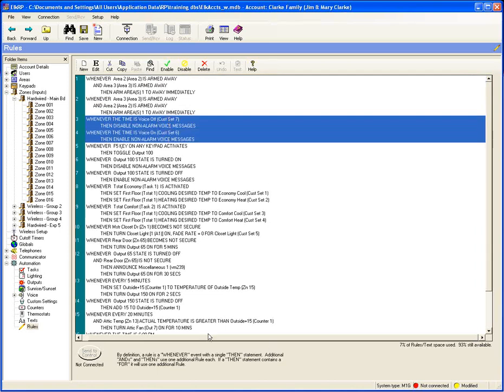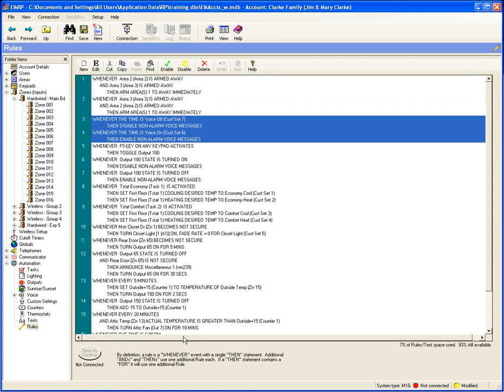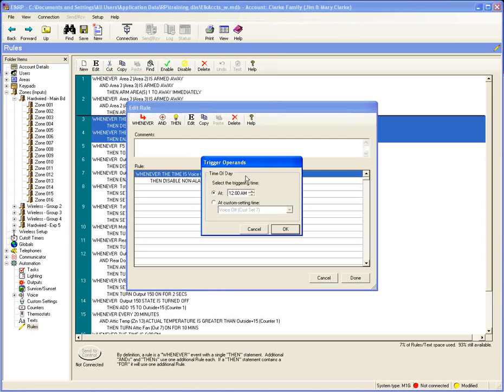Examples three and four are related to turning the voice on and off. The rule says 'disable non-alarm voice messages' — that means it disables only non-alarm messages; if there is an alarm, any voice messages for that alarm will still be heard. I've incorporated custom setting seven here, choosing 'at a custom setting time' instead of a specific time of day. This way, if your customer wants to change what time that occurs, they can do it themselves — you're giving them flexibility they'll really appreciate.